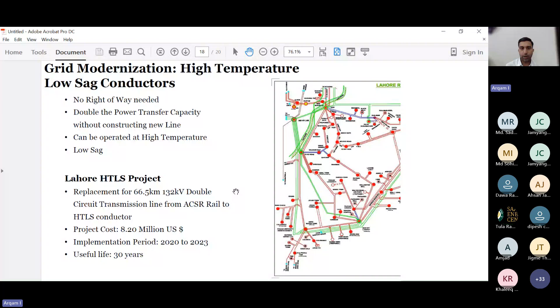So talking about a recent example from our experience in power systems, we have deployed almost 66.5 kilometers of 132 kV double circuit transmission line, which was on ACSR rail conductor, which we converted to HTLS conductor. So this is just a geographical layout of where we deployed this. This blue area is where we deployed these high temperature low sag conductors. This project was completed in 3 years, and it cost almost 8.2 million dollars. So this has a useful life of 30 years, so it can keep supplying almost double the power requirements without using any new right-of-way corridor.